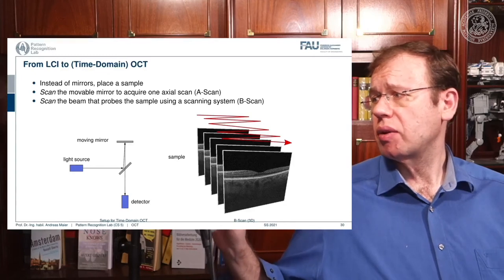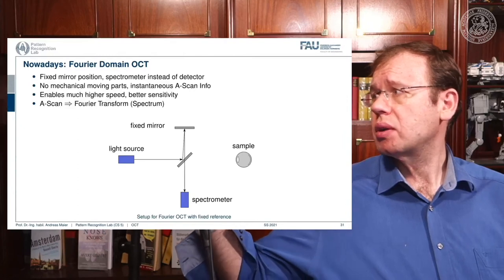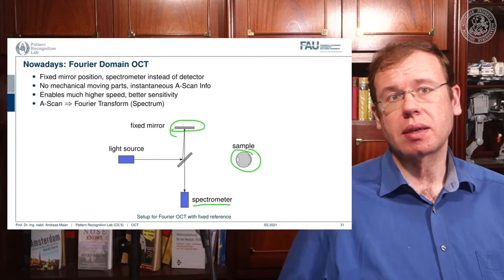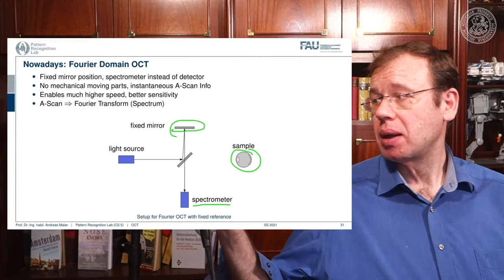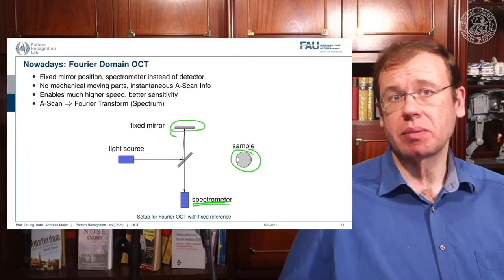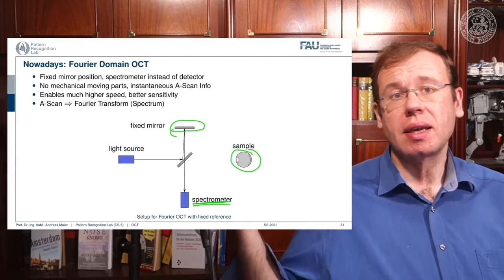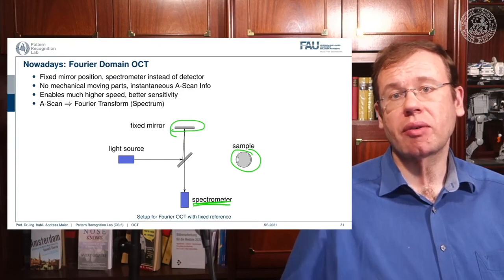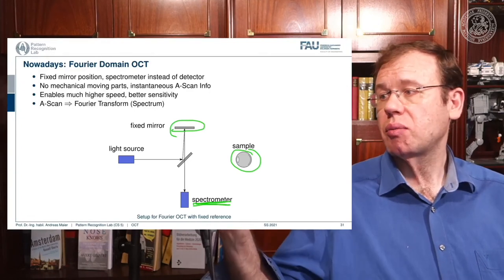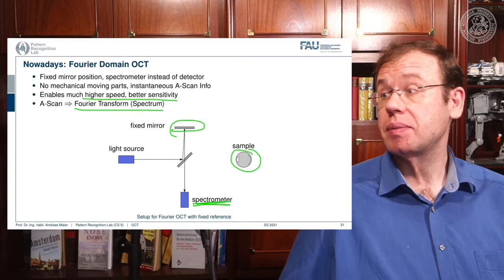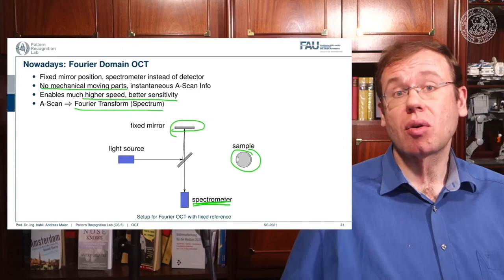Time domain OCT takes a little long and is not so efficient. This is why Fourier domain OCT is used: here you use a fixed mirror and a spectrometer. You analyze the spectrum of the single pulse sent in, measuring one A-scan with a single spectral measurement. If you need 1000 steps for an A-scan and can measure 1000 values at once with the spectrometer, you achieve a speed-up of a factor of 1000. The A-scan is obtained after a Fourier transform, since we're acquiring the Fourier transform of the desired depth profile. There are no mechanical moving parts, making the system more robust.